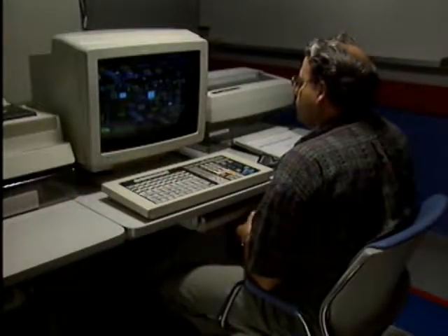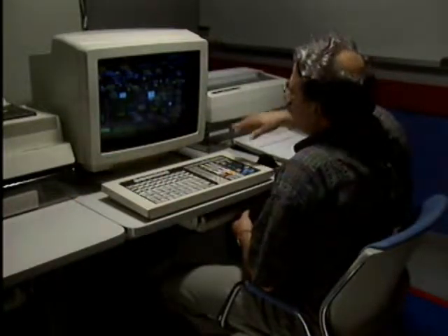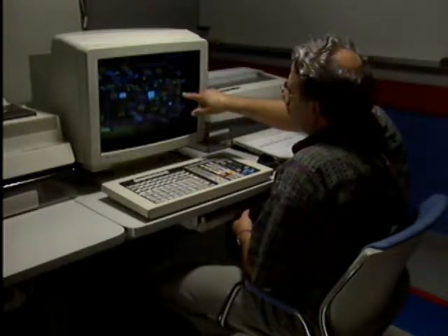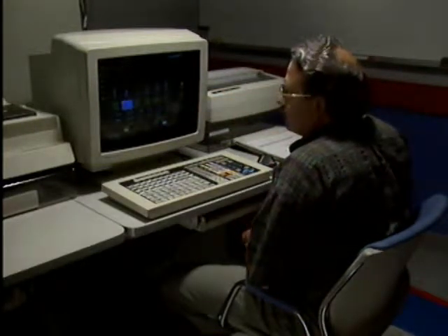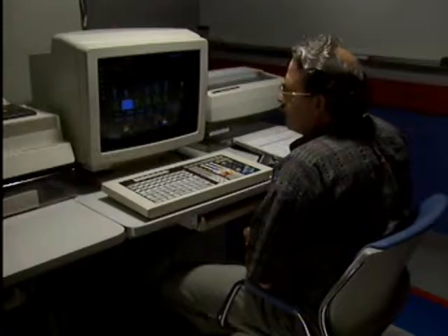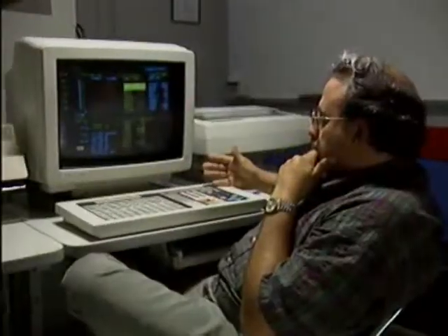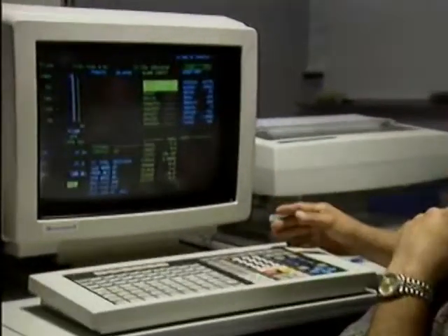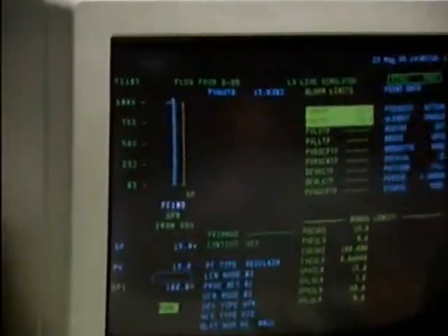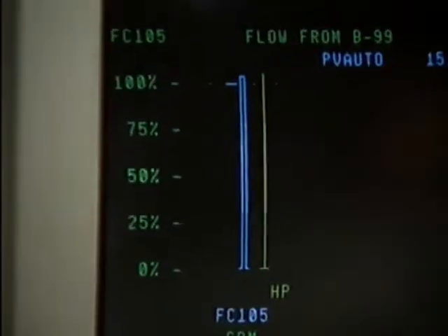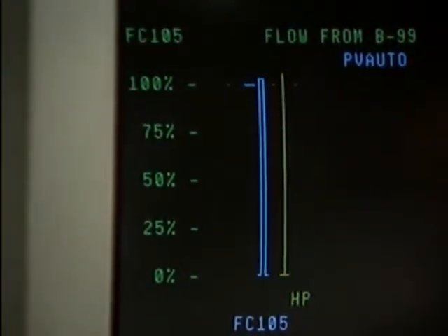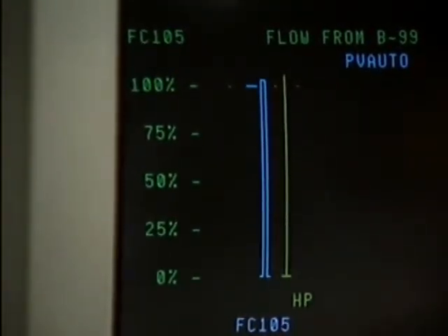The control room operator again checks the status of the process on the control system display screens and can find nothing wrong. Since he can find nothing wrong, he restarts the transfer of feed material and informs the outside operator of the restart. The operators know that their troubleshooting is not over. The control room operator attempts to increase the speed of the pump, but the pump is already at its maximum speed.